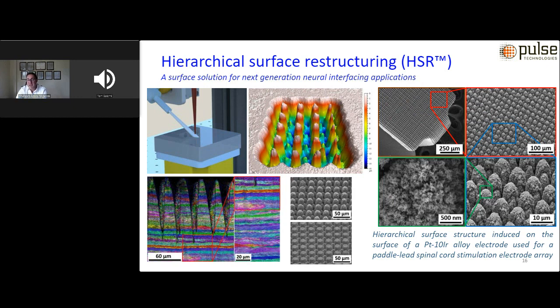Over the last several years, we have developed the applicability and performance benefits of femtosecond laser hierarchical surface restructuring technology. We have explored the tunability of performance as a function of several readily accessible laser parameters on a wide array of electrode materials and geometries for a large number of devices and applications. As an example, on the top right section of the slide, you can see the hierarchical surface structure that is induced on the surface of a platinum 10% iridium alloy electrode that is used for a paddle lead spinal cord stimulation electrode array.